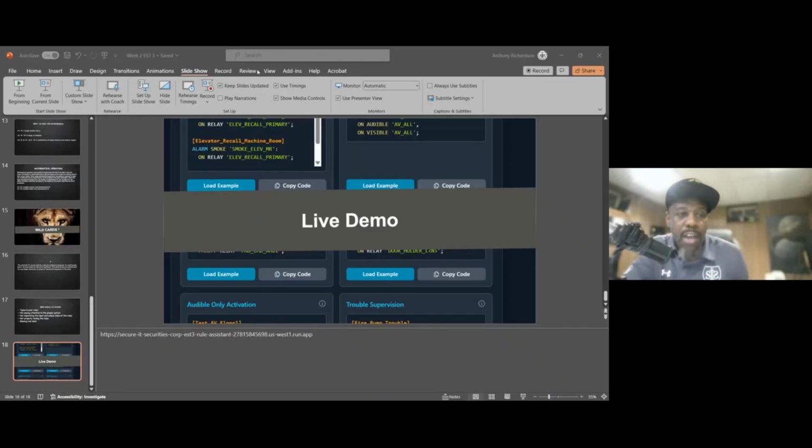And zone, this is how you would also group your devices into a zone if you were sending out zone by zone to central station. So you would put all your pull stations in one group. You will put all your smoke detectors into one group. You will put all your CO detectors into another group, water flows and tampers, and you would define these zones, and whatever those zones are, you hand those over to central station. So every time any one of those devices goes off in that particular zone, that zone will become active.